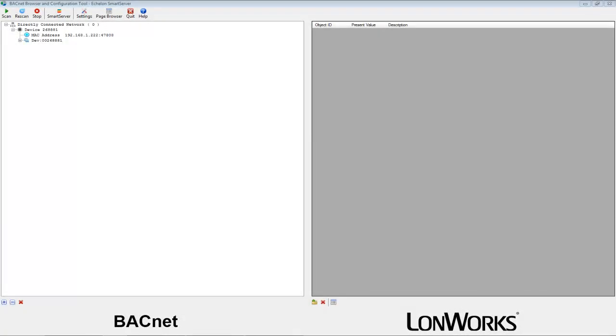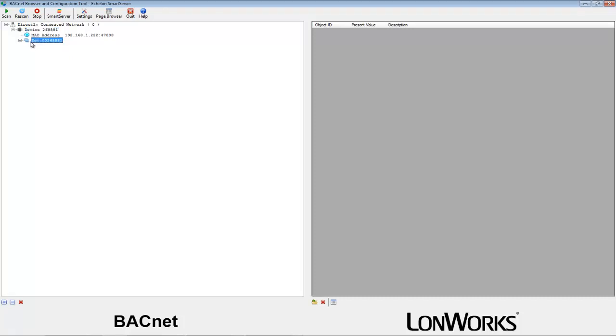Let's head back to the BACnet browser to create a configuration file. Notice that the discovery window in the browser may have discovered a single device. This is the app itself. Also notice that the device contains no objects other than a descriptor of itself. This is because there exists no configuration from which the app can generate points.